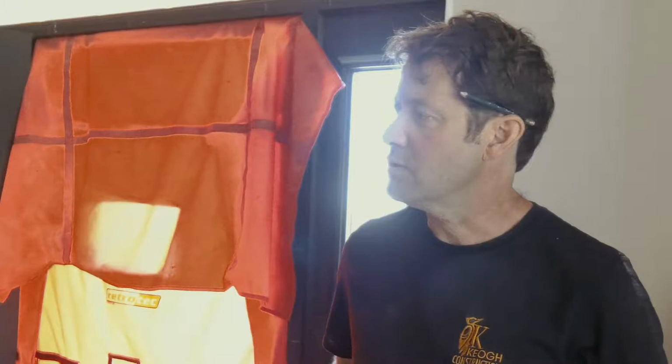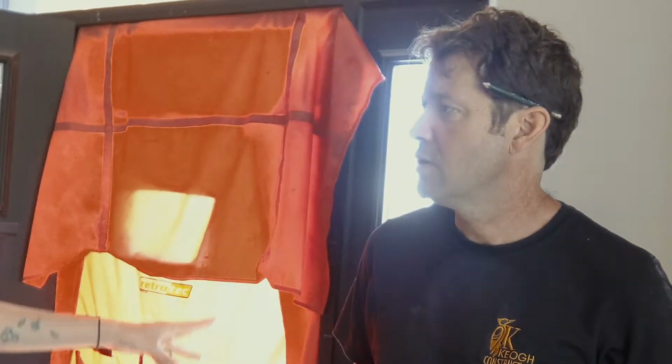And there are still some things that aren't done, like all of the trim within the house. That'll cut it down a little bit more. But really at 1.8 ACH, that's low enough that you're not worried about homeowner callbacks. We didn't find any really big holes. That's really the purpose.